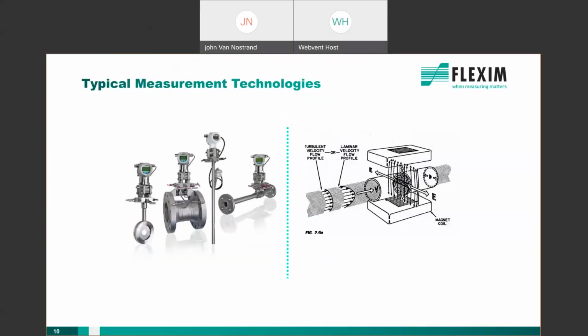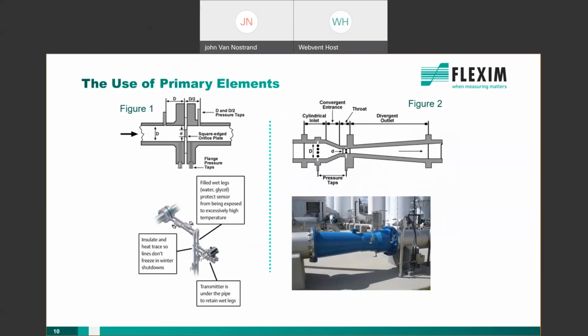So 2 common methods for measuring flow are primary elements and magnetic flow meters. Primary elements are often used in clean water applications, while magnetic flow meters, although they started out in dirty liquids, are now commonplace in clean water as well. Let's take a little closer look. First, the primary elements, or DP flow meters as they're often known.